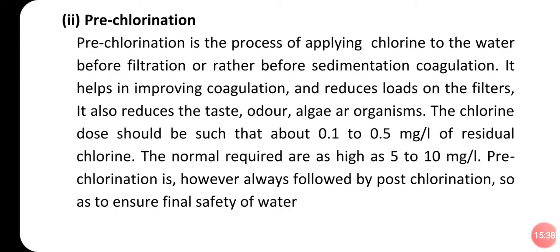But what is the normal dose then? The normal required dose is as high as 5 to 10 milligram per liter. If you apply 5 to 10 milligram per liter, you should see that the residual chlorine is 0.1 to 0.5 milligram per liter. This is called pre-chlorination. One important point to remember: pre-chlorination is done before sedimentation or before filtration. So that is called pre-chlorination.